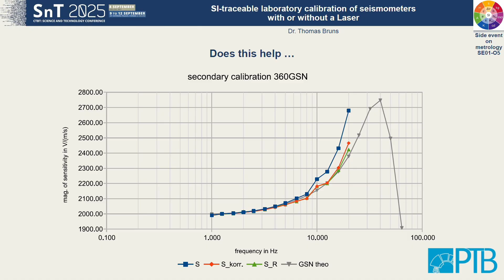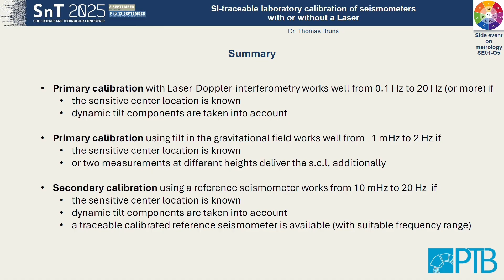So in summary, primary calibration with laser Doppler interferometry works well in the typical frequency range here from 0.1 Hertz to 20 Hertz or more if the sensitive center location is known. This is something that I would try to advertise to manufacturers in the room. Think about whether you can make this a specification in your data sheet. It will be very fundamental for good calibrations, primary and secondary.